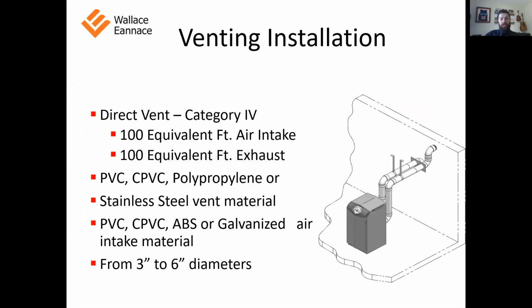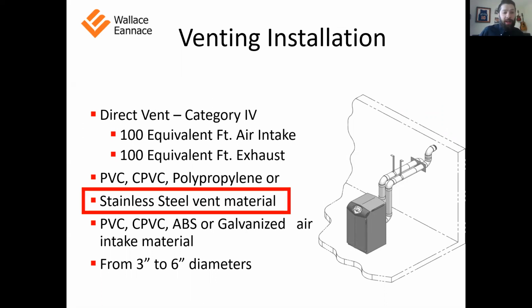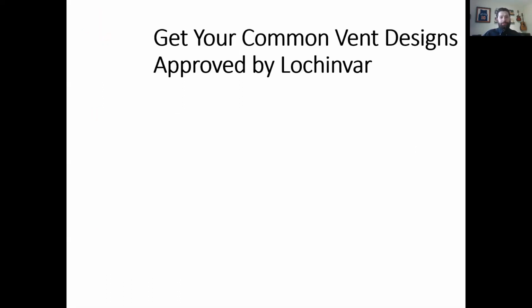So for your venting installation, direct vent category 4, with most of these units, you can do 100 equivalent feet, meaning each elbow is going to cost you about 5 feet, a 90 degree about 2.5 feet. So you can do about 100 equivalent feet with the fan installed in the unit. According to the IOM, you can use PVC, CPVC, polypro, stainless steel, a lot of different ones, 3 to 6 inch diameters. This is on the Knights. But in New York City, and always check local code, guys, wherever you're installing, we're going to use mostly stainless steel, AL 29-4C for the most part. That's what you're going to be using.